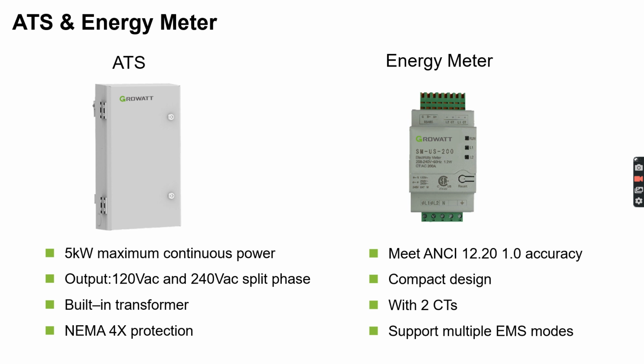The ATS will be connected to both the grid and inverter backup port. Initially, when the grid is available, backup loads will be powered from the main panel, but in a blackout situation, the ATS will switch over to the connections of the backup inverter, allowing for continuous power to backup loads in all scenarios.